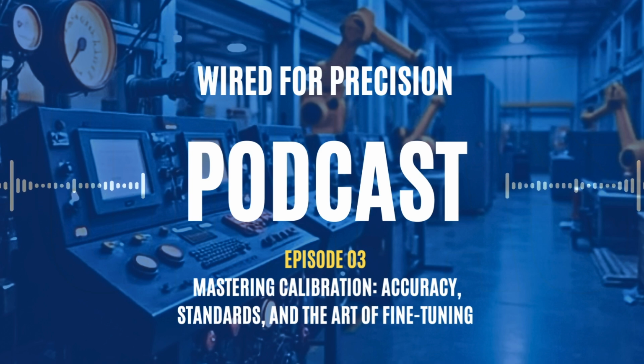Let's clear up some confusion. Verification checks if the instrument's readings fall within an acceptable tolerance. Calibration is the comparison against a known standard. Adjustment is the act of tweaking the instrument to correct any deviation found. You can verify without adjusting. You can calibrate and still choose not to adjust, depending on whether the error is within limits.